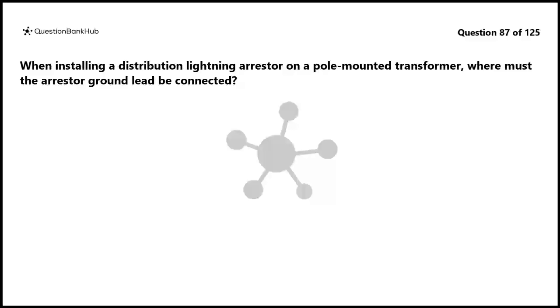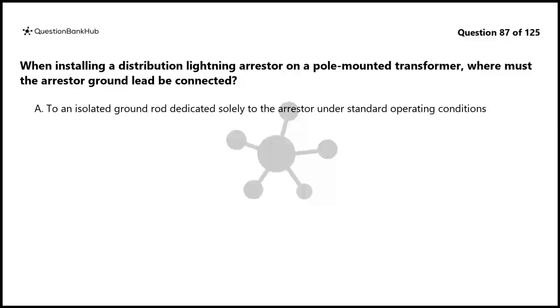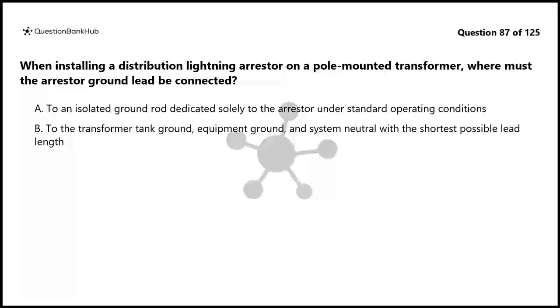Question 87. When installing a distribution lightning arrestor on a pole-mounted transformer, where must the arrestor ground lead be connected? A. To an isolated ground rod dedicated solely to the arrestor under standard operating conditions. B. To the transformer tank ground, equipment ground, and system neutral with the shortest possible lead length.